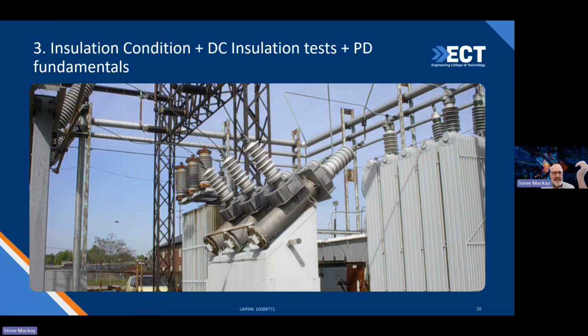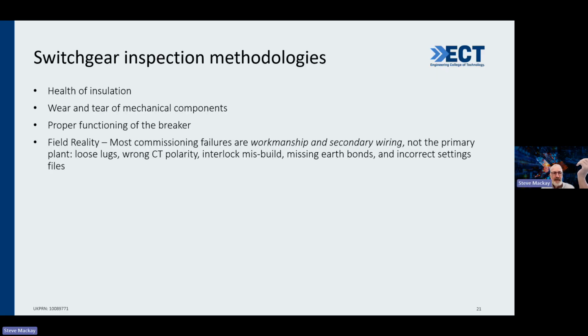And obviously some of the things we'll be looking at are insulation condition, DC insulation tests, partial discharge fundamentals, and obviously switchgear inspection methodologies, quite important. And I don't know, are we able to text in the box here? We're all happy texting. Obviously, people aren't texting. So obviously, with switchgear you look at the health of insulation, the wear and tear of mechanical components, proper functioning of the breaker, and obviously the field reality, really important.